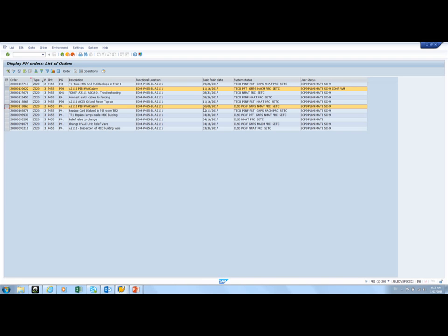Well, if I'm getting high PIB alarms in for this area and we're doing regular PPMs, something is wrong, and it's telling me that I have to check something. Obviously that PM we're doing in that area is not adequate, and this is an old job, and I've picked this one specifically because when we investigated this, I know there's only 2 jobs, we found that some equipment was not included in the PPM routine. We have fixed it and we haven't had these alarms since. That's just what I wanted to show you.